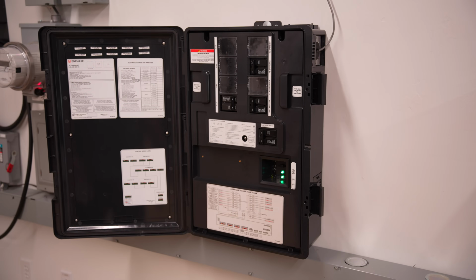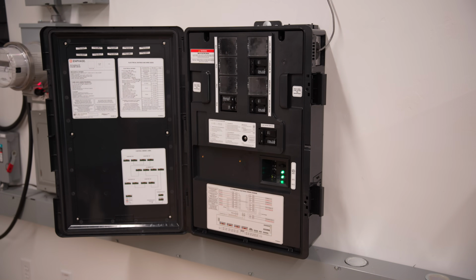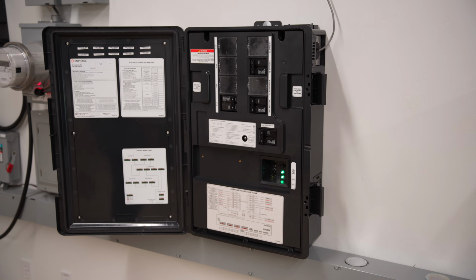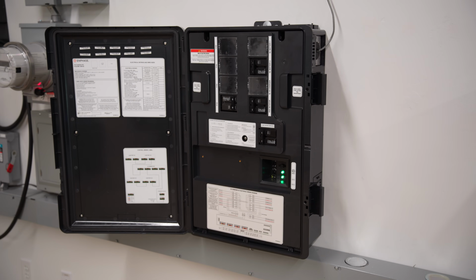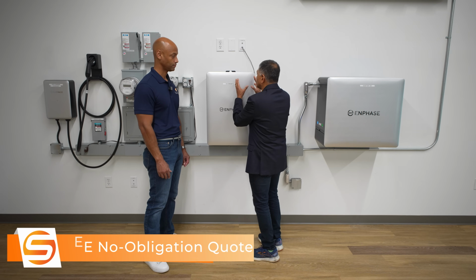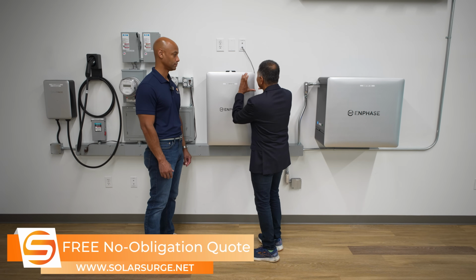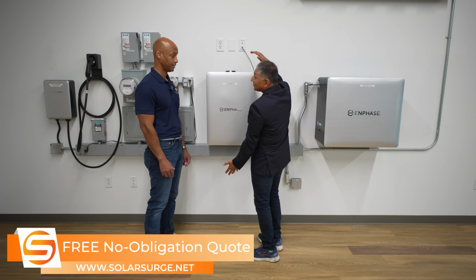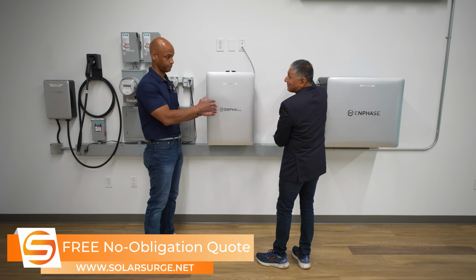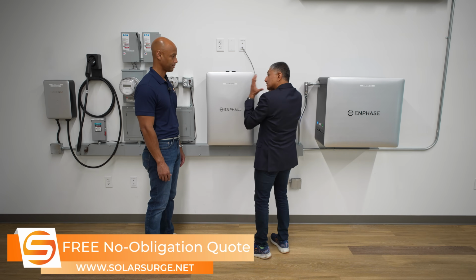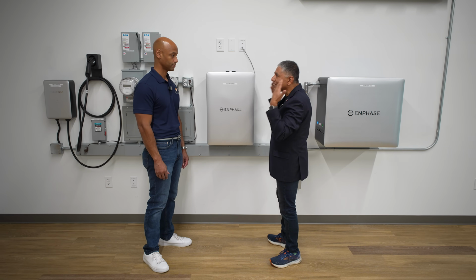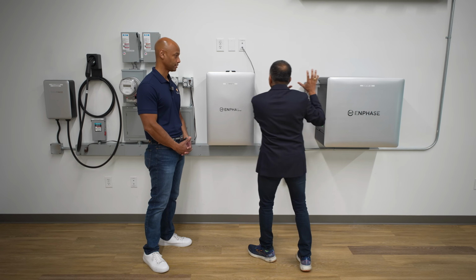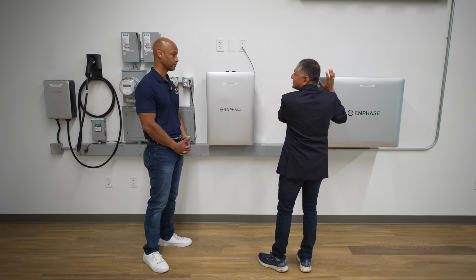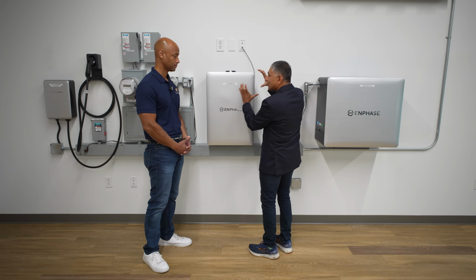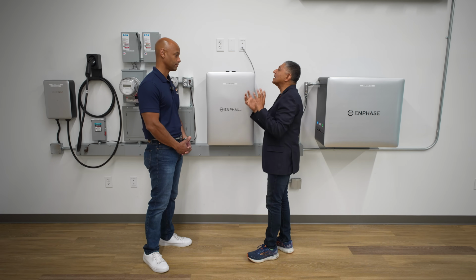This is the point of aggregation. The actual MID function, which was the isolation device that used to be inside the system controller, created a limitation—it forced a co-location problem, meaning that system controller, which was a very big unit, had to be placed right next to the main panel, very close to the service entrance. We took that MID function—part of the decentralization thinking we always have—and said, the MID is a standalone function, let it do its MID function: if the grid is not present, open the MID. We took that function and put it inside a meter collar.